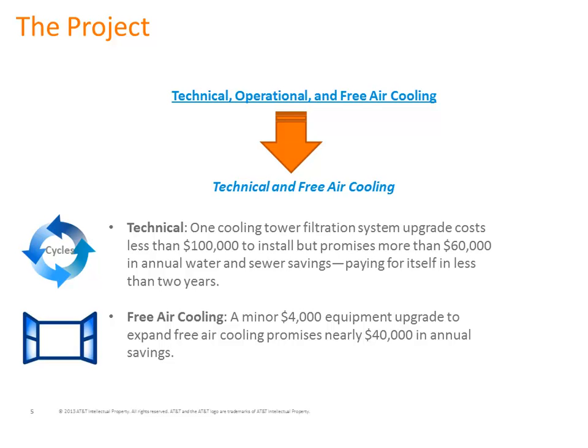On the water side, we saw very significant drops in water usage, with a near 70% reduction in sewer discharge and a 29% reduction in our water usage in the cooling system overall. So, a very, very successful pilot there.